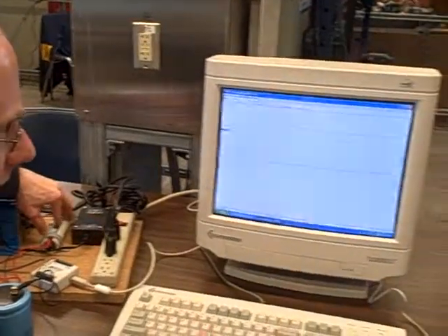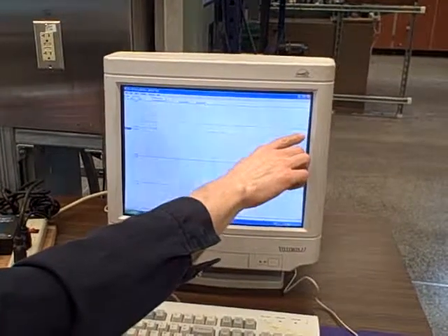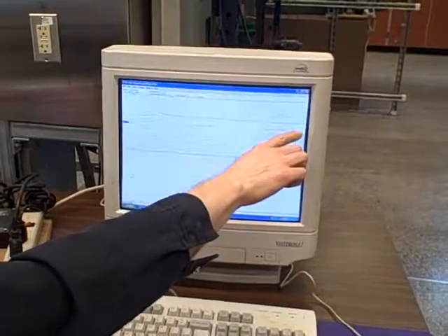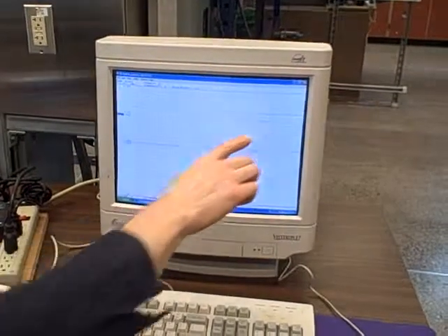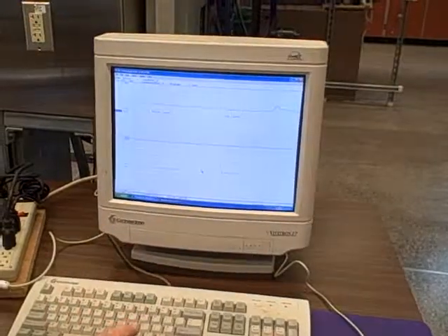Now if I slow it down with my finger, it responds quicker. It tries to keep it to set point much more aggressively than before. If I let go, it overshoots and then comes back to set point quite rapidly compared to what it did before.